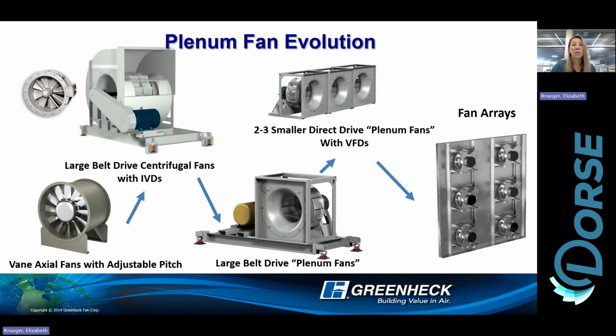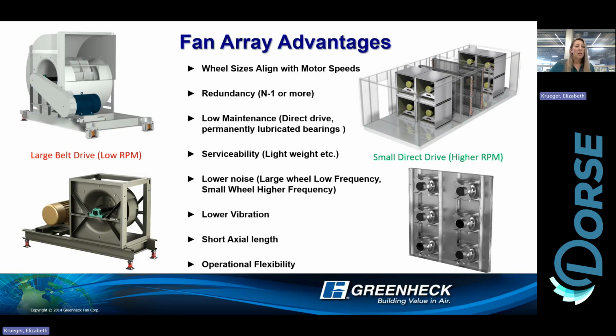I know fan arrays are associated a lot with data centers, but what we've been seeing sweep across the country right now is retrofitting air handlers. So, going through just some fan array advantages. I talked about the redundancy. There are smaller wheel sizes, smaller motor sizes, and it's easier to change those motors out. I mean, imagine trying to change out a 100-horse motor on this big double wide guy over here. Some of those have just giant motors on them, whereas with these, you have your small individual motors, or in the case down at the bottom, sometimes you just change out the motor fan in this one panel there.